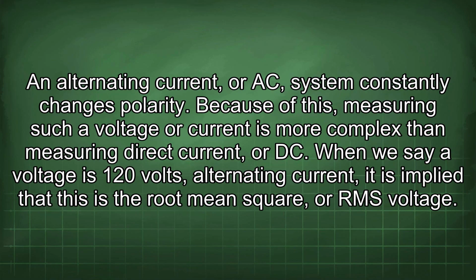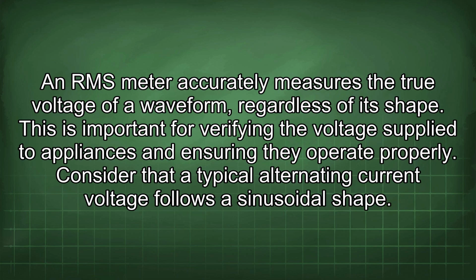An alternating current, or AC, system constantly changes polarity. Because of this, measuring such a voltage or current is more complex than measuring direct current, or DC. When we say a voltage is 120 volts alternating current, it is implied that this is the root mean square, or RMS voltage. An RMS meter accurately measures the true voltage of a waveform, regardless of its shape. This is important for verifying the voltage supplied to appliances and ensuring they operate properly.